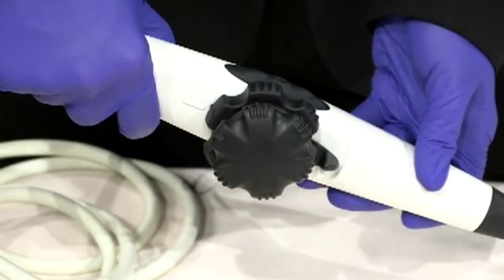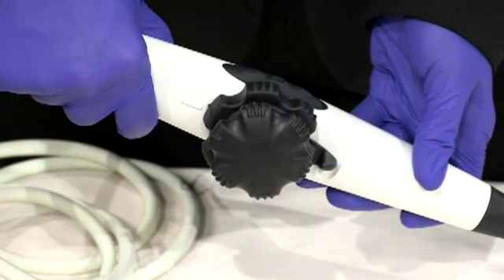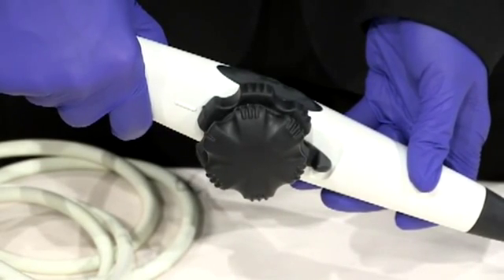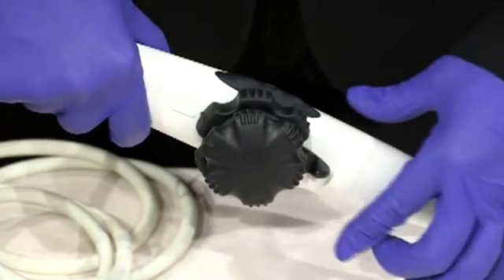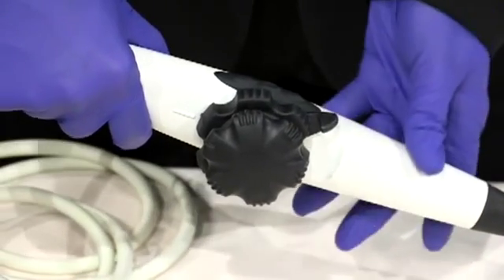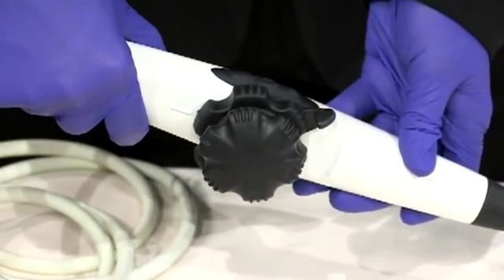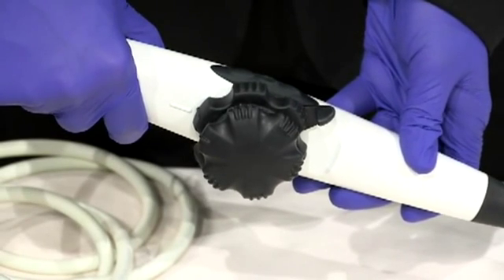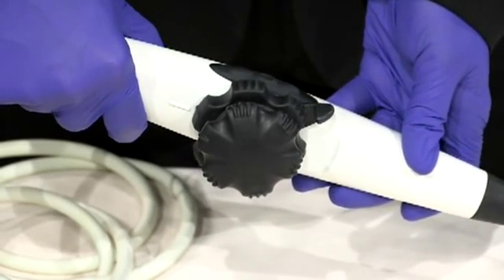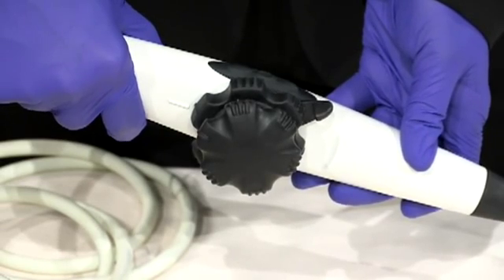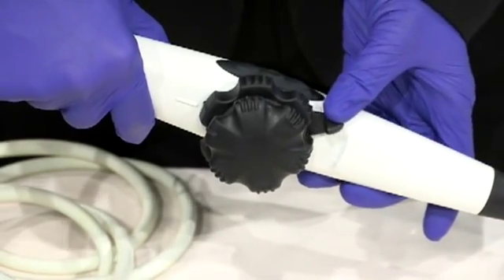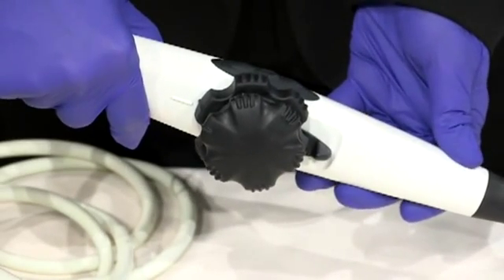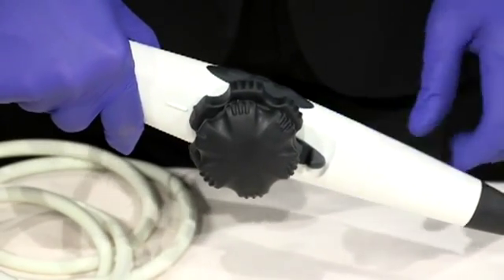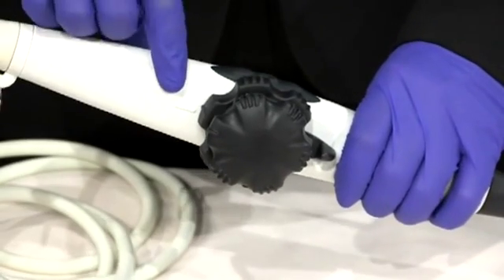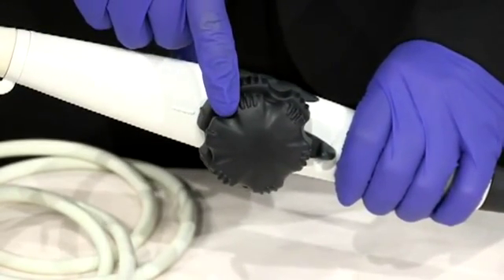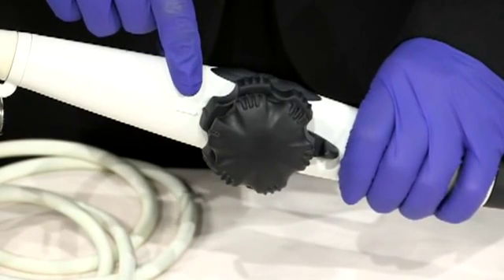To be able to retain the tip deflection in a position, friction can be applied to the up-down deflection control. The TEE deflection brake will hold the up-down deflection position if no force is applied to the scan head. It is important to note that the friction brake is by no means a locking mechanism. This is to ensure that the endoscope will straighten if the probe is rapidly removed in a critical situation. Also note the neutral position markers indicated on the probe handle and knobs. Neutral position is indicated when the markers are aligned.